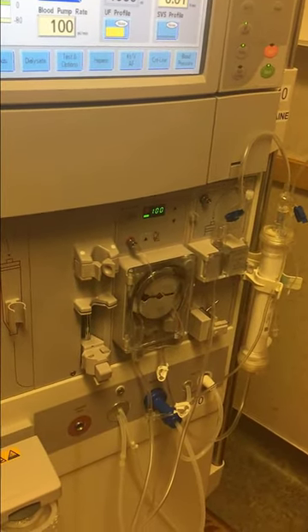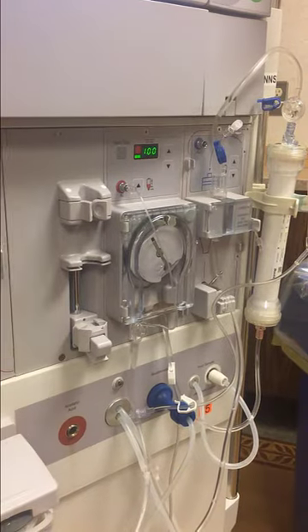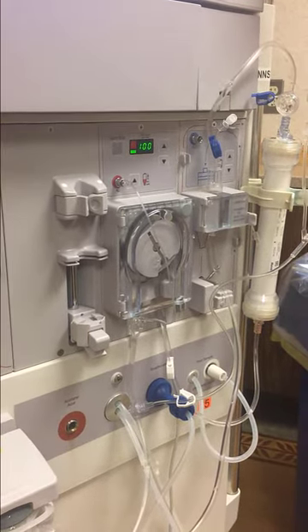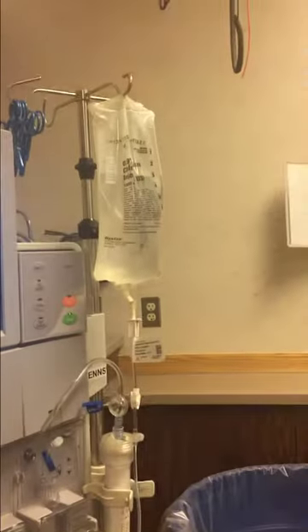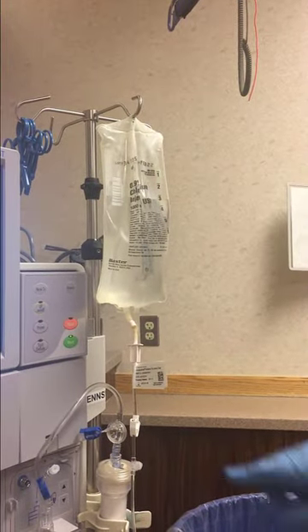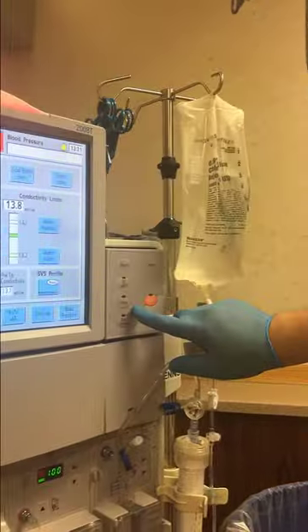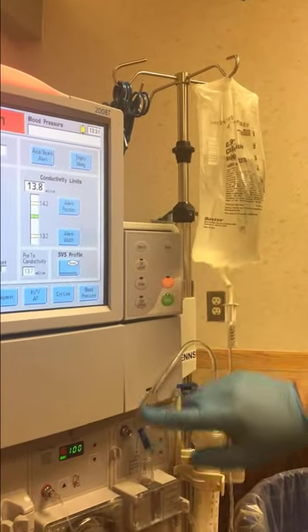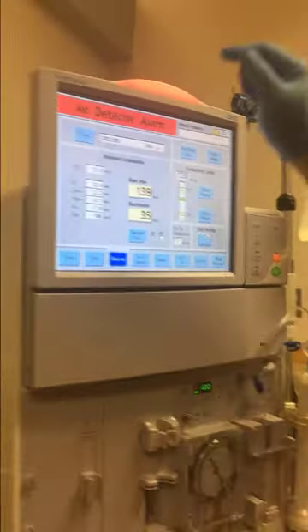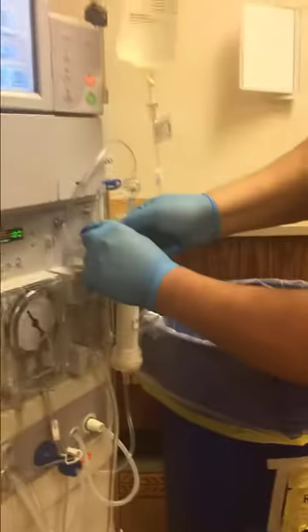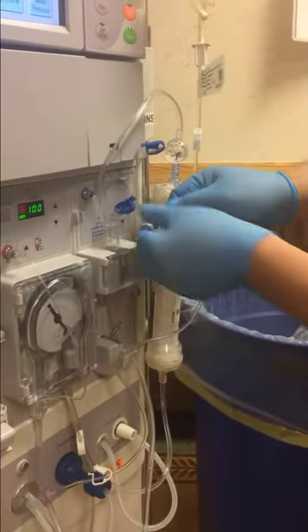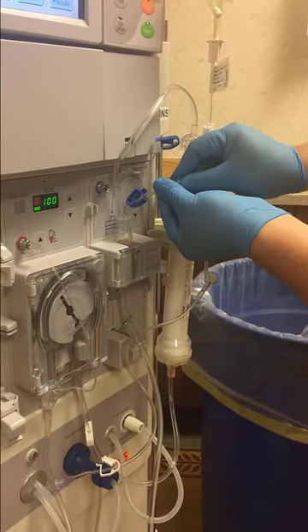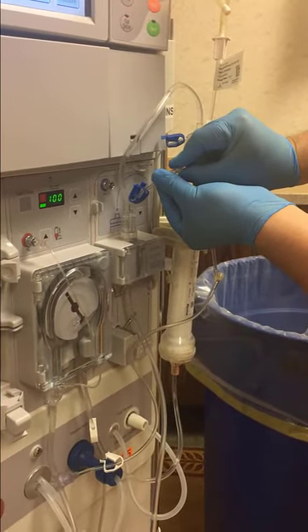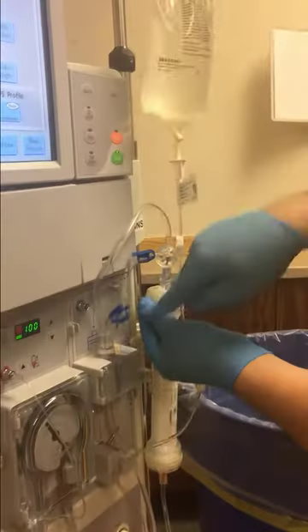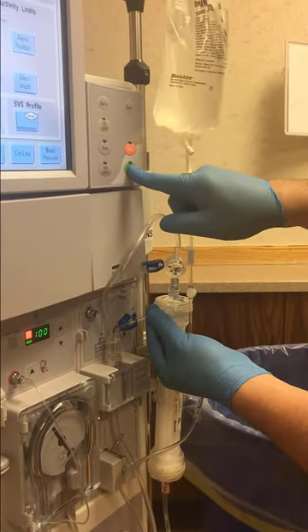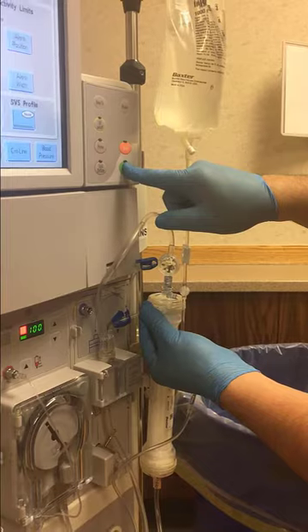The machine will run through a prescribed volume that is set by Biomed. So once that completes, the pump will stop. And now you're ready to get the machine set for test. So in order to test the machine, you're going to finish filling your venous trap. You want to make sure all of the air is out of it. And then you're going to thread your venous line clamp into the machine.